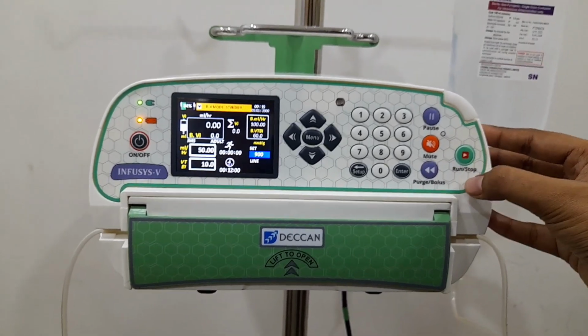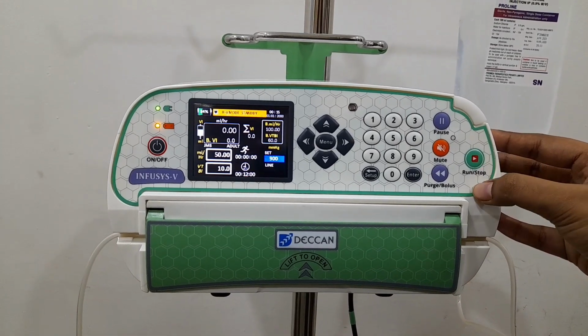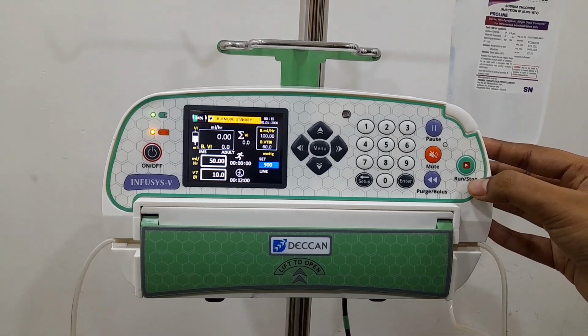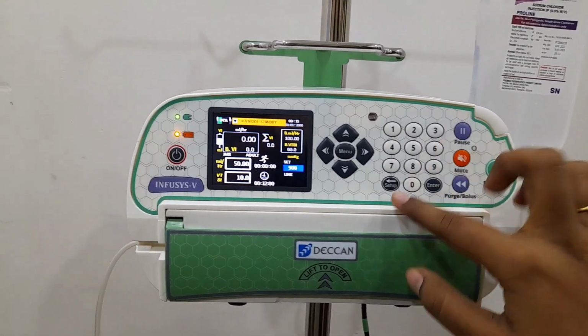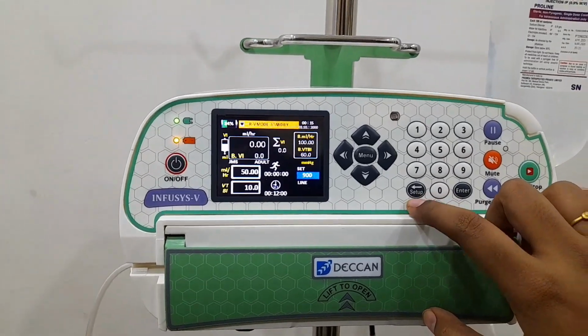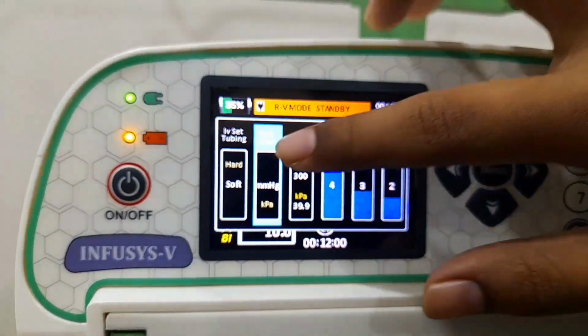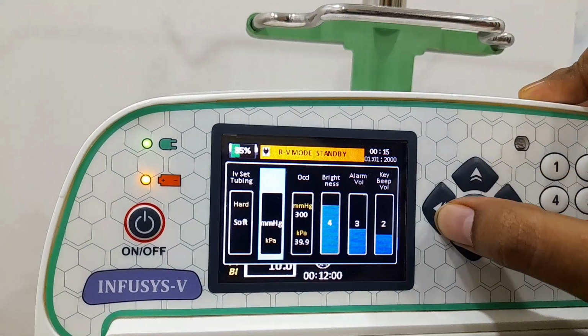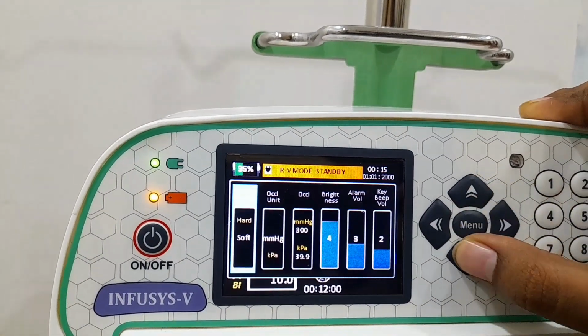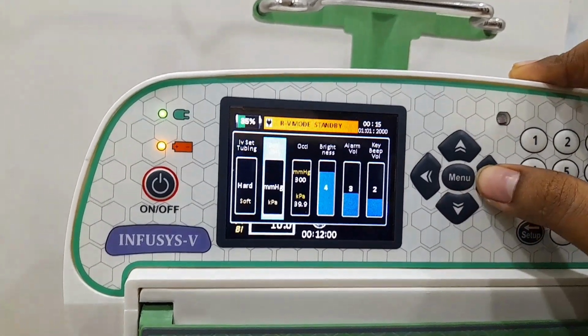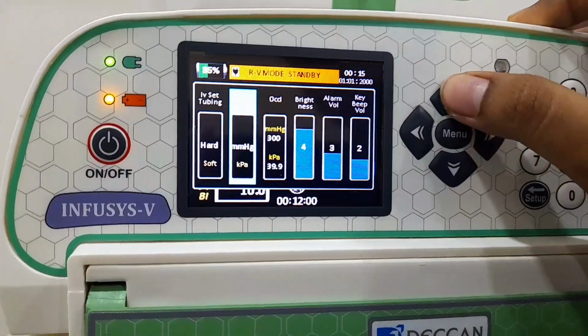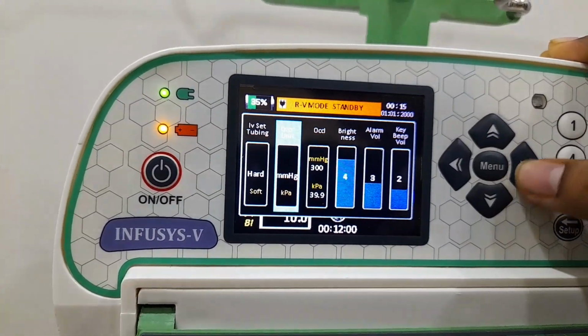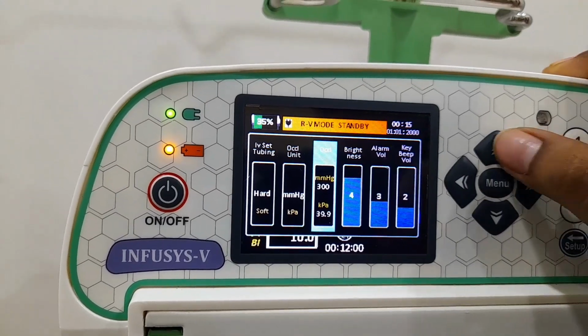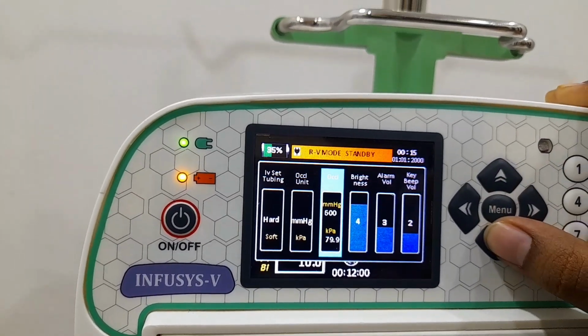And run or stop key. The run or stop key is used to run or stop the function. We move to the setup key, quick setup. Press quick setup. Here we can see the IV set tubing, hard or soft. Select the option using the up and down navigation key, and occlusion unit like mmHg and kPa, and occlusion high level, low level and medium level, and brightness level.